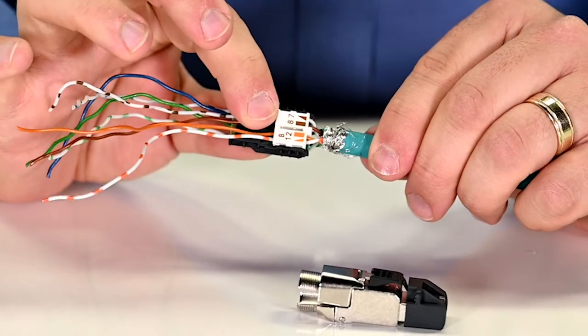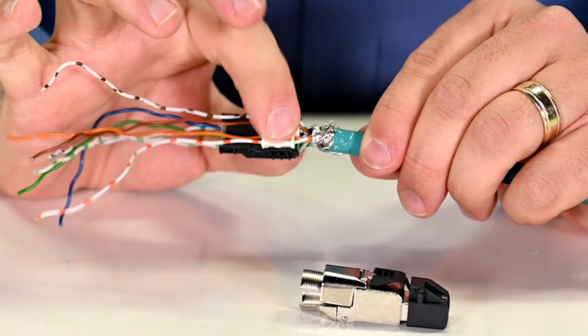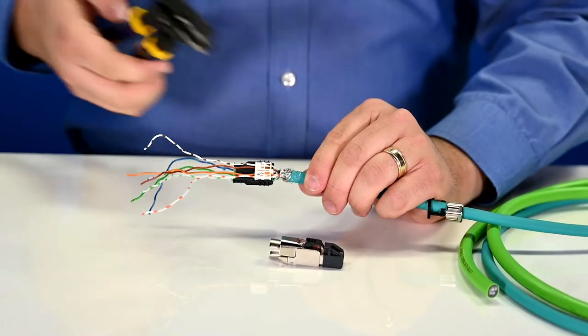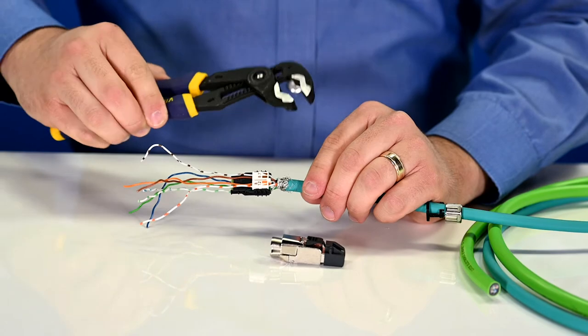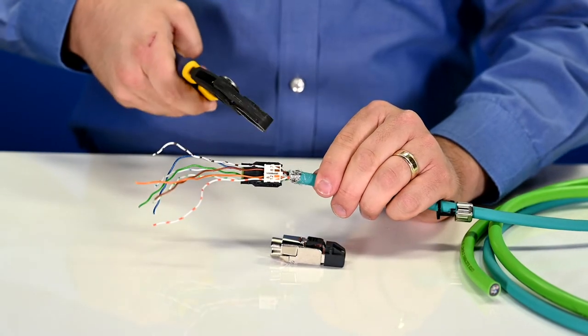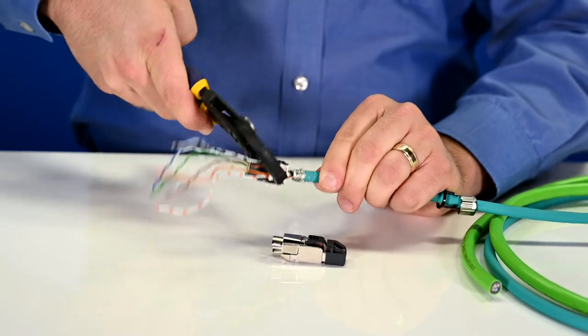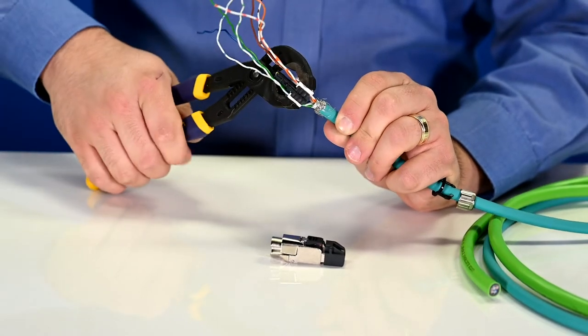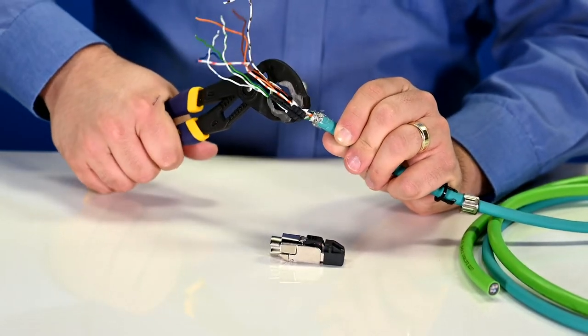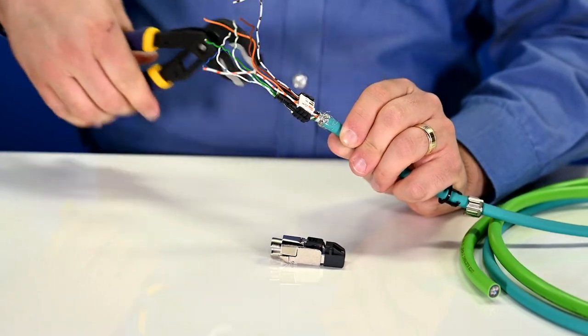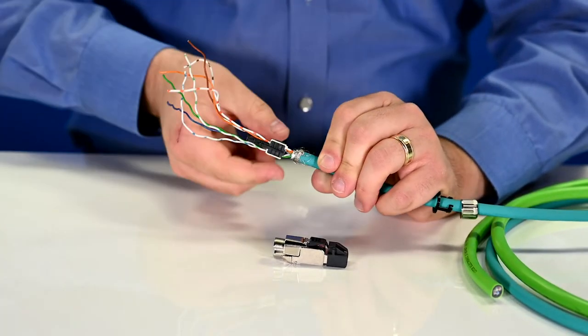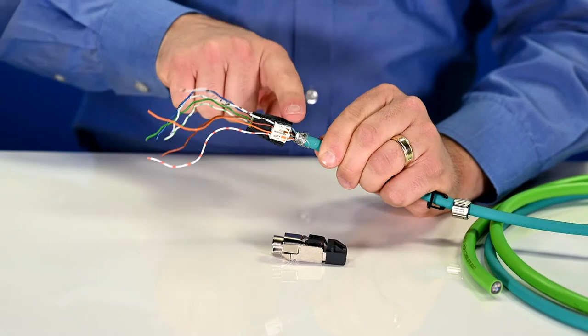Now that we have that nice and tight, it's time to engage those contacts that we talked about. And all you need to do this is a pair of channel locks or something else that applies parallel clamping force. So we want something that's going to put pressure on either side of that connector, and we simply clamp straight down. Make a nice firm connection, and you see that also loosens up this protective plastic housing.